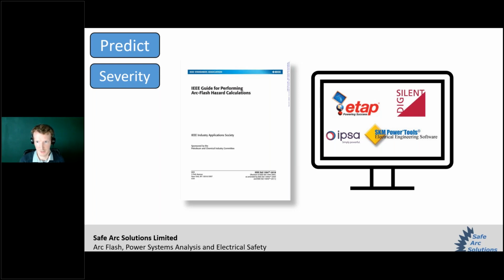The IEEE working group for this commissioned thousands of laboratory arc flash tests to generate a whole bunch of empirical data around the energy released by arcs under different voltages and currents and equipment configurations. And bringing all this data together allowed them to then statistically analyze it and develop a set of equations that allow for extrapolation, interpolation to apply these to a wide range of electrical equipment, including UK equipment. It's perfectly applicable here. The equations then have been built into popular electrical power analysis software, which allows for arc flash calculations to be run on a computer alongside your other system studies like load flow and short circuit.